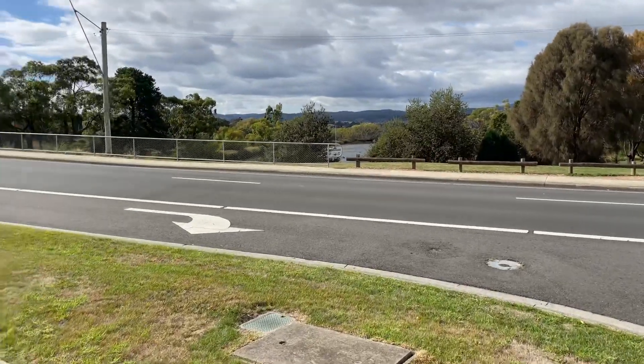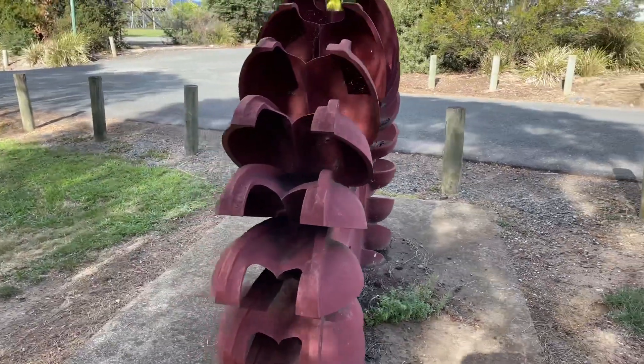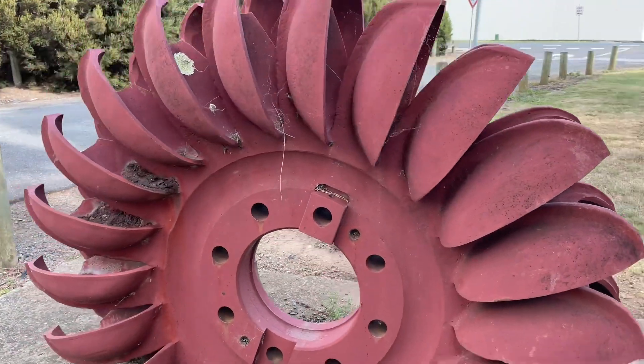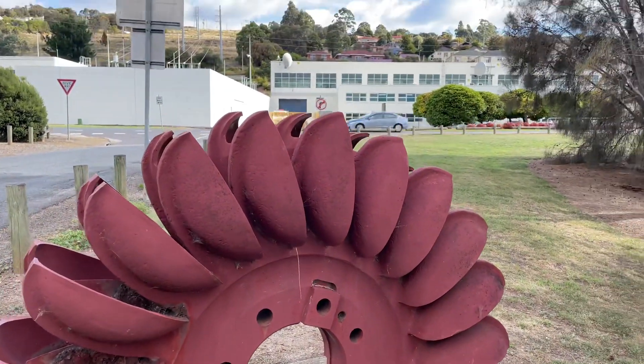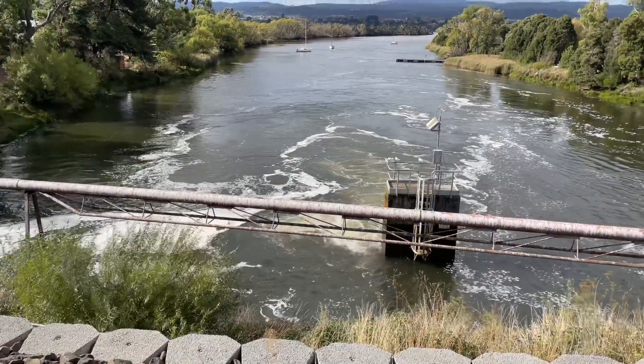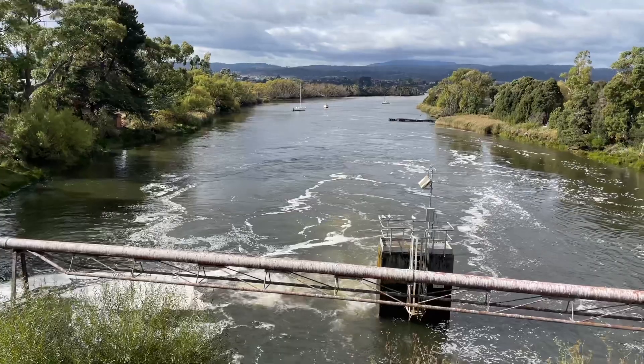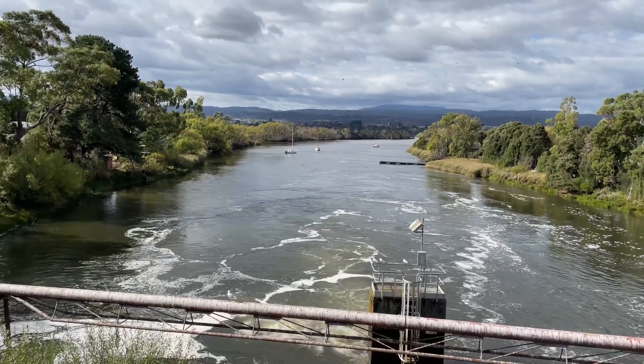So effectively, it's a flood mitigation or bypass system. This is a Pelton Wheel — it's what powers the power stations. The water flows down the penstocks at high speed, hits those buckets, turns the generator, which in turn generates the electricity. You can see here the water's bubbling away into what's known as a tail race. It comes out of the power station, into this tail race, and out to the lower part, or the estuary part, of the Tamar River, thus protecting Launceston from floods.